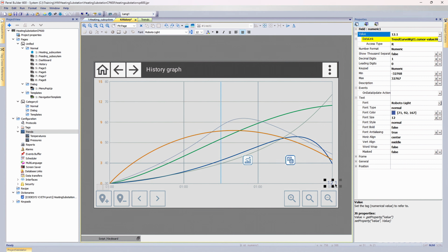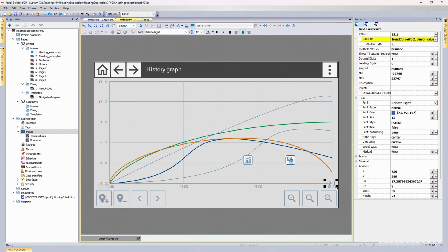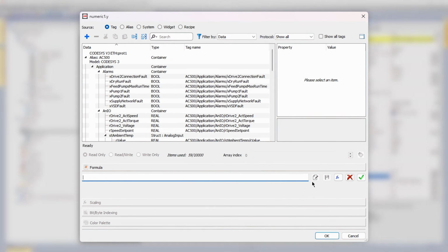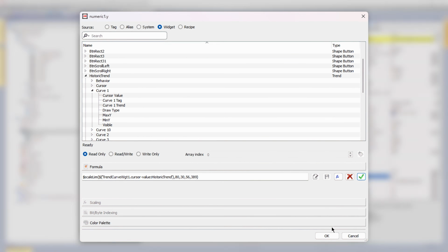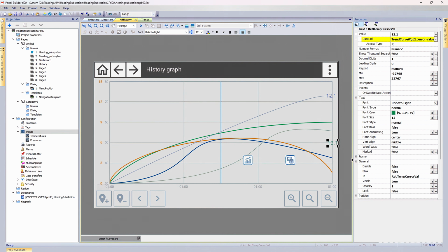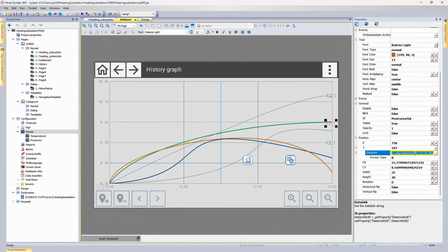I could just leave it sitting statically below the graph, but let's make it a bit more intuitive. I'll move the numeric field over to the right edge and mark the vertical positions for the scale's minimum and maximum. Then I'll use those coordinates to make the widget slide up and down vertically. We used this exact same trick in the last chapter to move a needle. Remember? Now we just repeat those same steps for curve 2, return temperature, and curve 5, discharge pressure. The logic is identical, but keep an eye on the min and max pressure values.